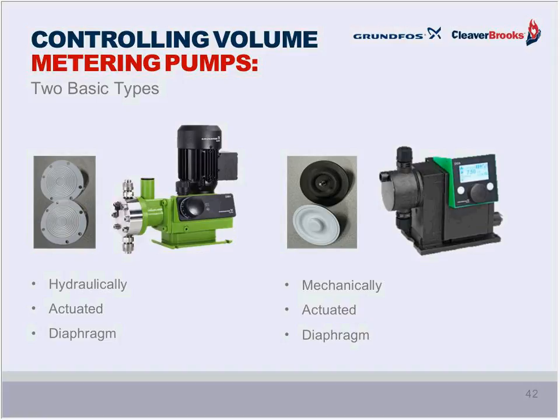The considerations for selecting dosing pumps in the boiler system are: 1, how high is the pressure in the line we're injecting into? And 2, is the liquid source located above the pump or below it, so that there's a suction lift, meaning bringing liquid from the tank up to the dosing head of the pump. Pumps are generally speaking good for up to around 300 psi, but this varies widely. If, for instance, the pump must be made of composite material such as PVC or Kynar, or it could be stainless steel. The metal is generally good for higher pressures, while the composite ones may be good for around 150 psi or so. These are general ranges with many exceptions.